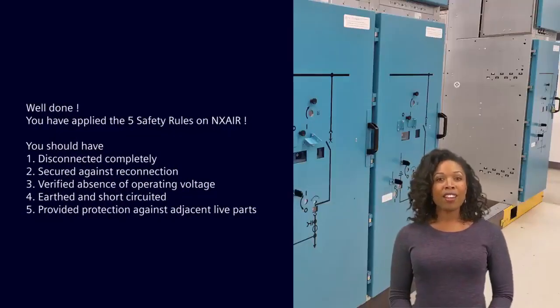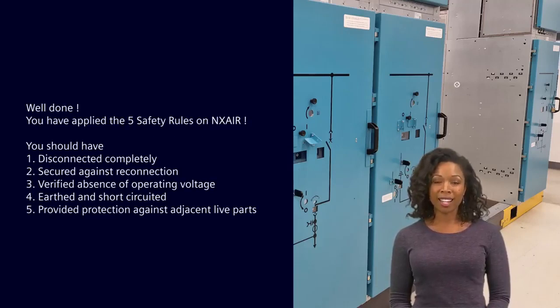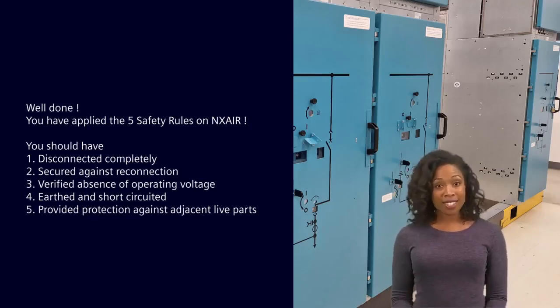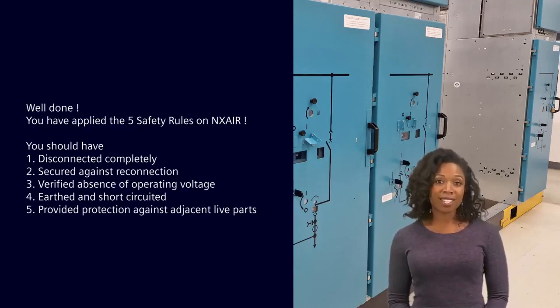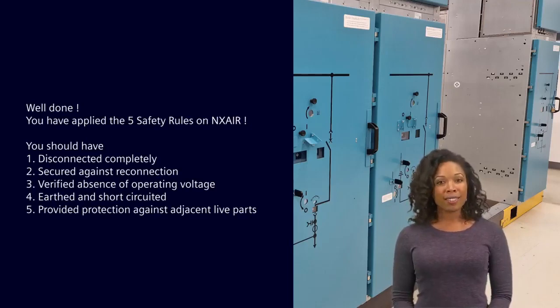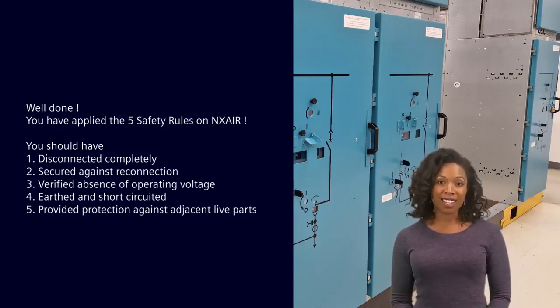The following 5 rules will help you maintain your NXAIR Switchgear in a safe and de-energized environment. Until verified, all electrical sources are assumed to be energized. Step 1. Disconnect completely. Step 2. Secure against reconnection. Step 3. Verify absence of operating voltage. Step 4. Earth and short circuit. Step 5. Provide protection against adjacent live parts.